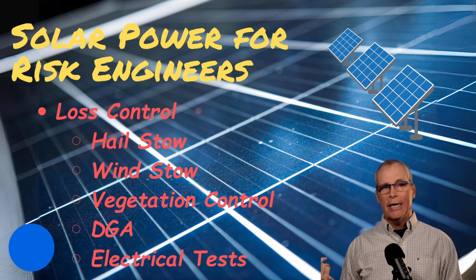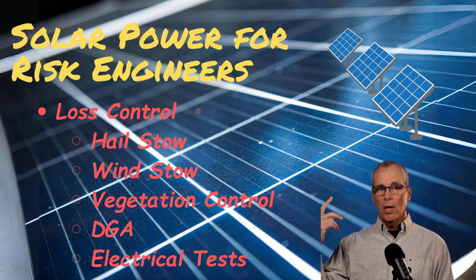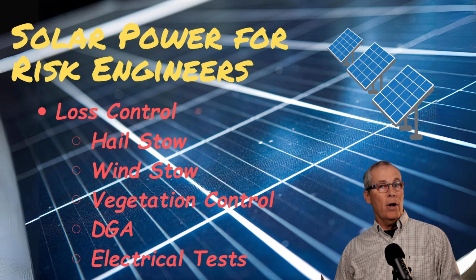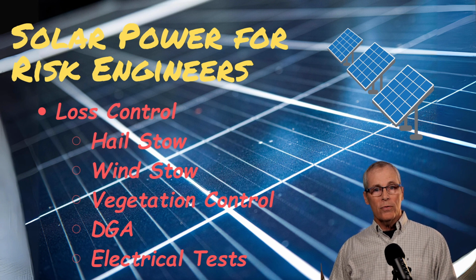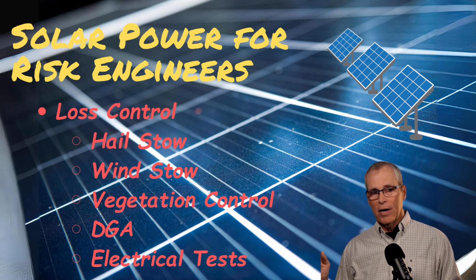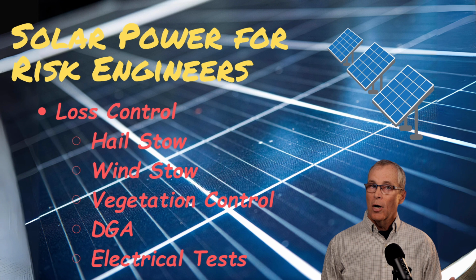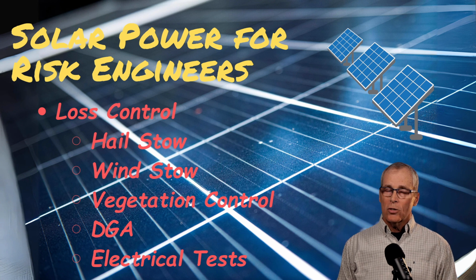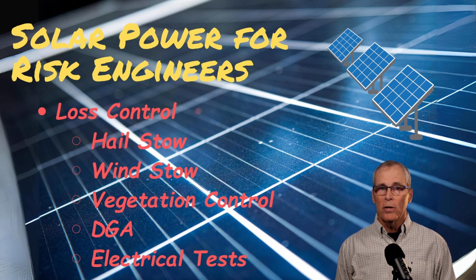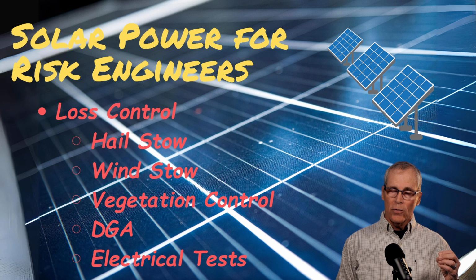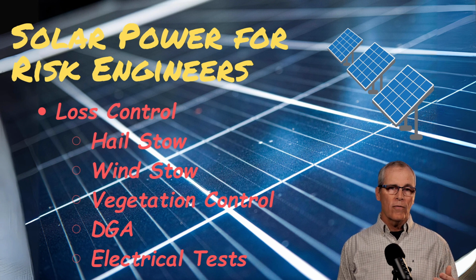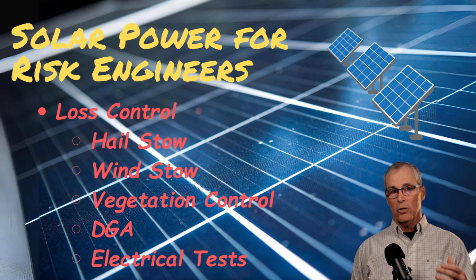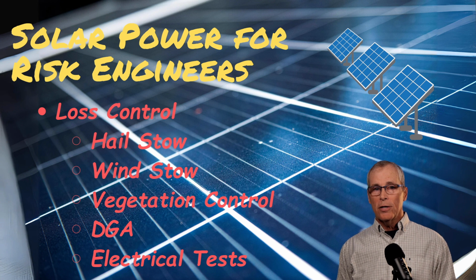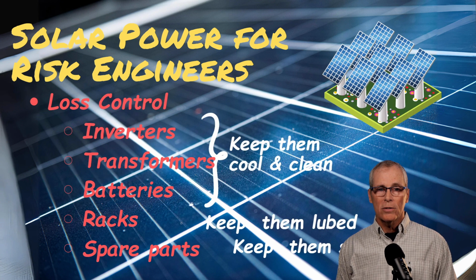That's fine, do that. But you need to get under the panels. You need to see those connectors that aren't visible to the drone. And you need to see what's going on around the grass level underneath those panels. So the drone is fine, but it's not going to prevent all these fires. So maintain the electrical equipment, do dissolved gas analysis. That's for the transformers. And like I've said before, I've got another entire video on the channel about transformer risk management and how to deal with and read dissolved gas analysis.